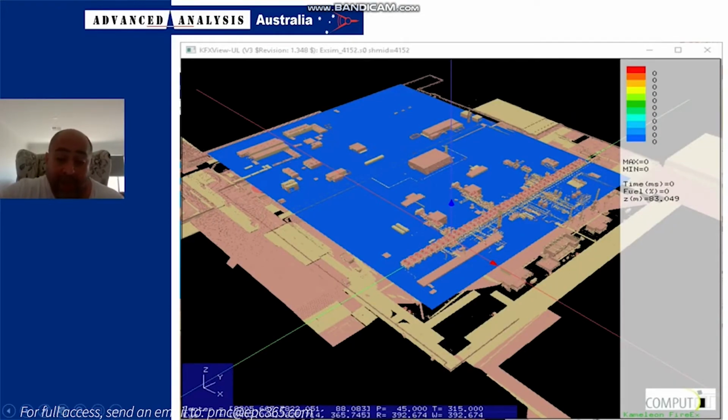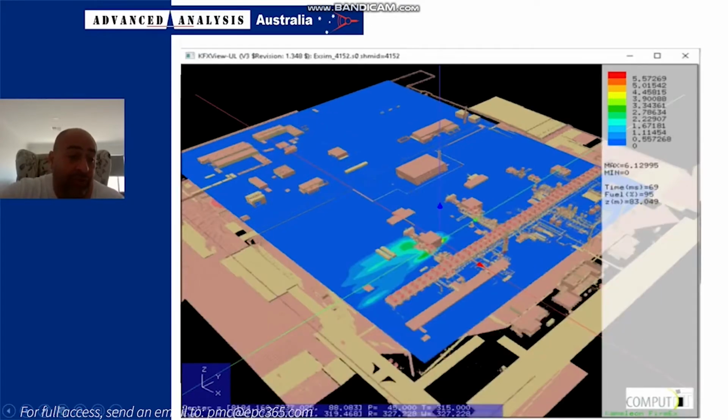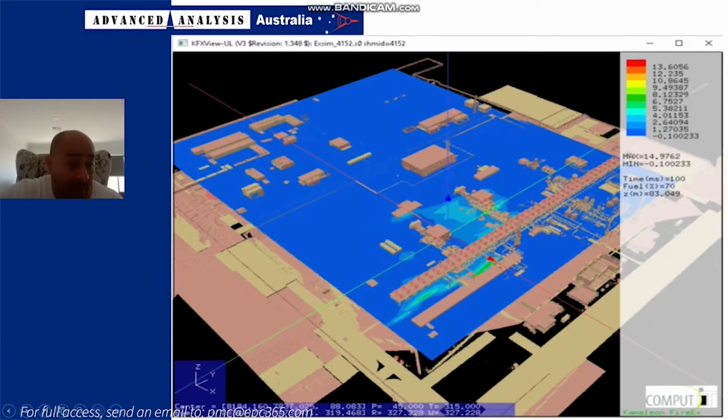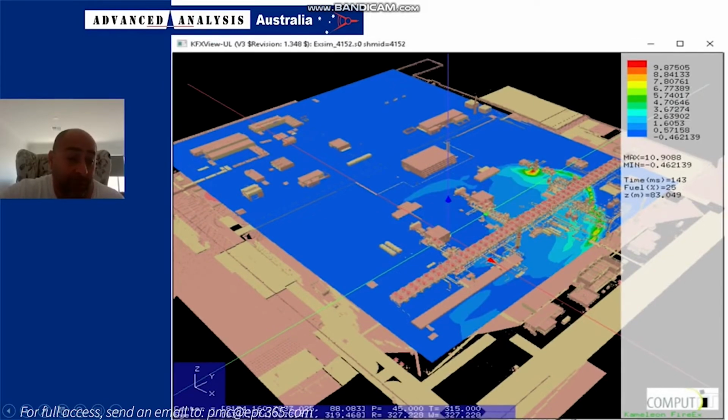In the past, to do a gas explosion using CFD, you basically had to model the site in 3 dimensions. That's expensive, it's time-consuming, it may not always be possible, and in fact, the end result of 3D CFD used for explosions has a large uncertainty.